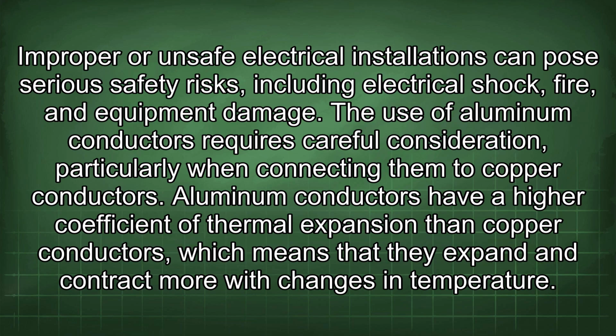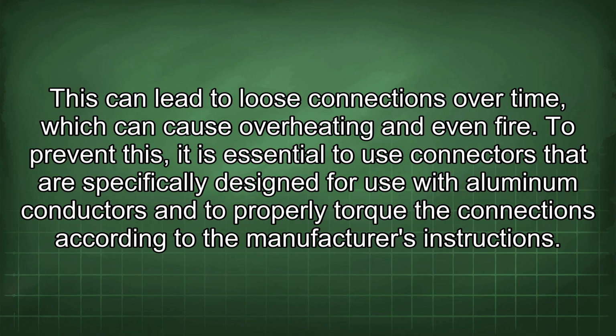The use of aluminum conductors requires careful consideration, particularly when connecting them to copper conductors. Aluminum conductors have a higher coefficient of thermal expansion than copper conductors, which means that they expand and contract more with changes in temperature. This can lead to loose connections over time, which can cause overheating and even fire. To prevent this, it is essential to use connectors that are specifically designed for use with aluminum conductors and to properly torque the connections according to the manufacturer's instructions.